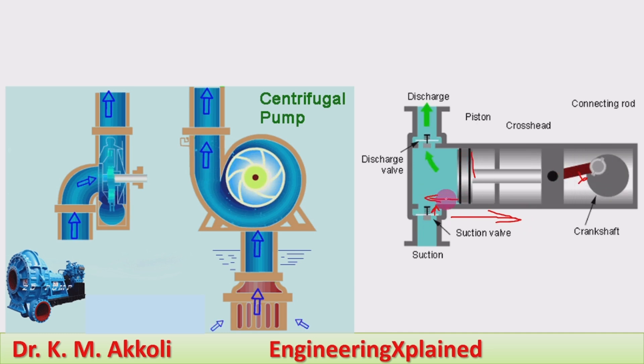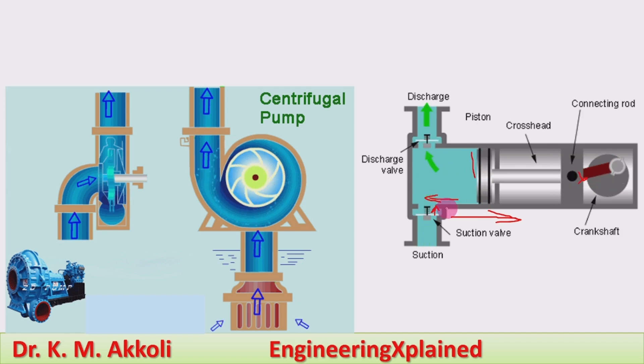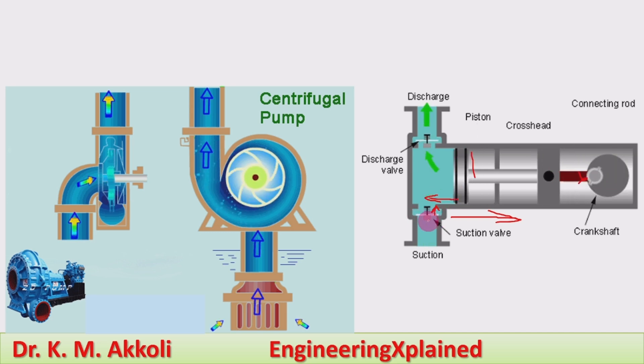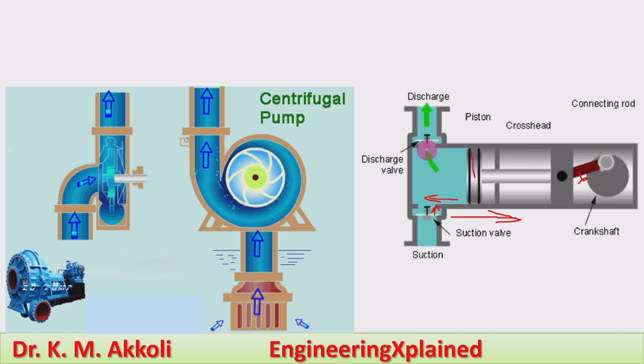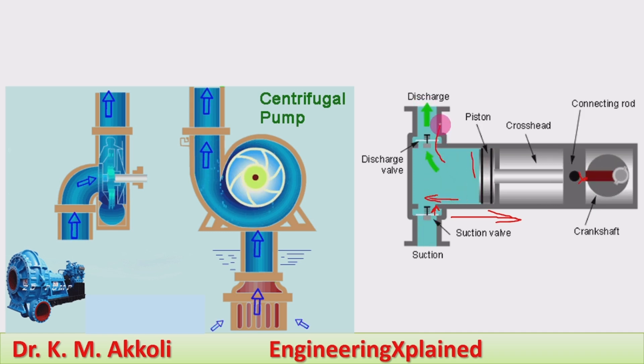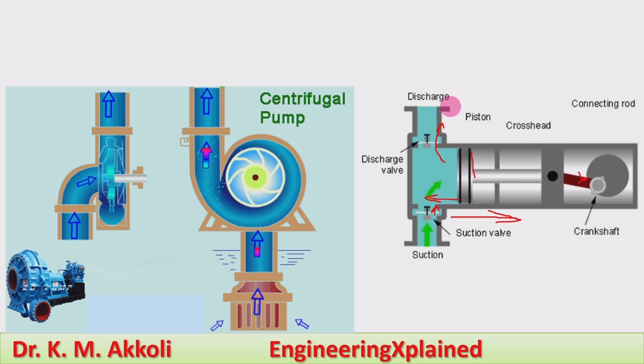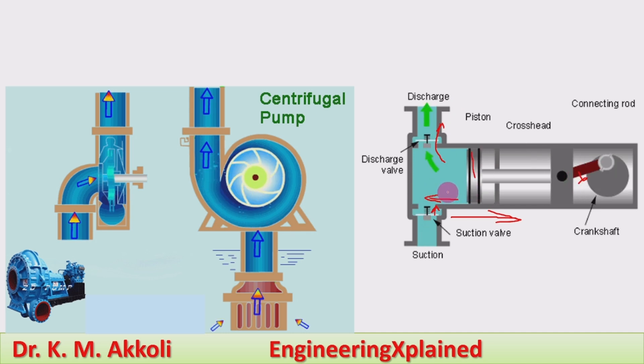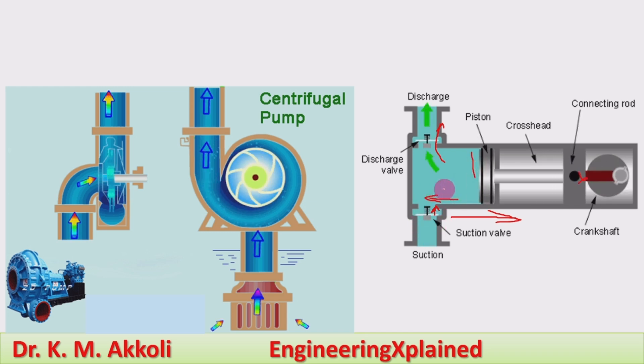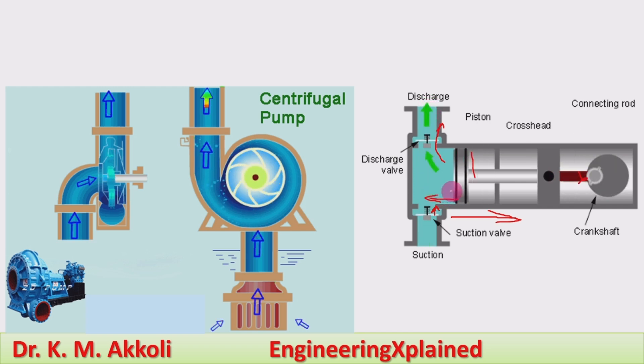When the piston is moving forward, it pressurizes the fluid inside the cylinder. During that time, due to the pressure, the suction valve gets closed — we can see how the valve element sits on the valve seat. The delivery valve opens and flow of fluid takes place to the delivery or discharge line. This reciprocating motion of the piston is continuous, so fluid keeps entering the cylinder and discharging — though the flow will be slightly fluctuating.